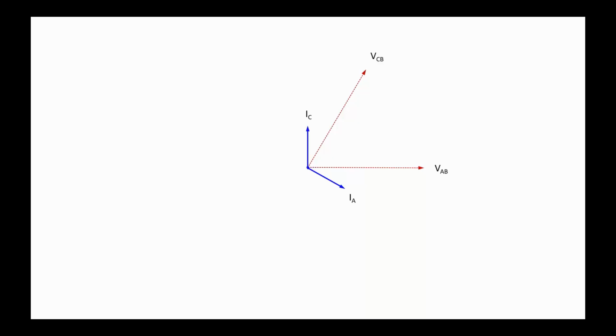If you were looking at VB to C, you would see it 120 degrees in the lower left-hand corner of the screen. But this is the 60-degree relationship that you typically see when you're looking at the inputs on a 2-element wattmeter. So I think that's an illustrative sequence of vector slides for something that's not otherwise intuitive.